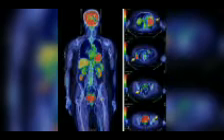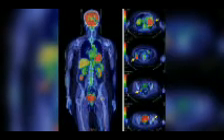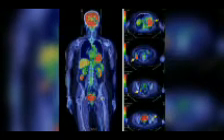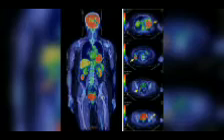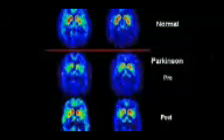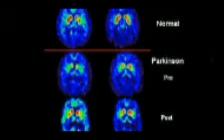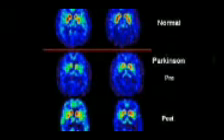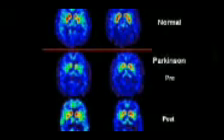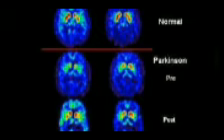Two major sources of noise in PET are scatter, a detected pair of photons, at least one of which was deflected from its original path by interaction with matter in the field of view, leading to the pair being assigned to an incorrect line of response, and random events, photons originating from two different annihilation events but incorrectly recorded as a coincidence pair because their arrival at their respective detectors occurred within a coincidence timing window.